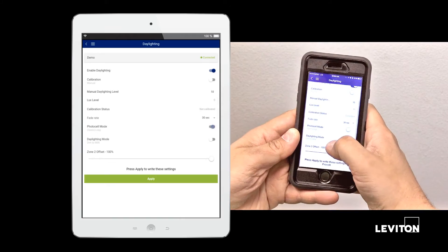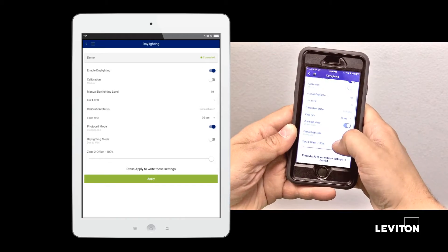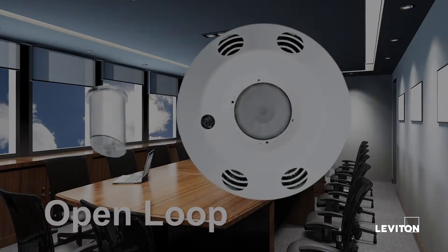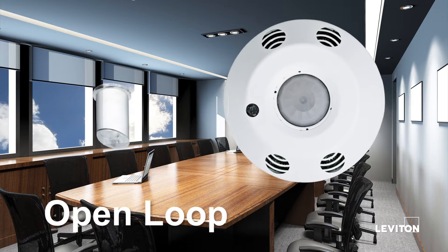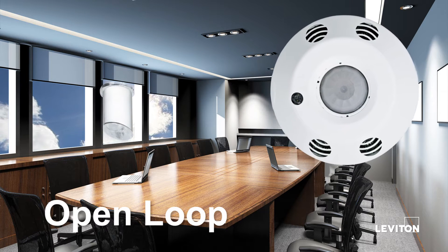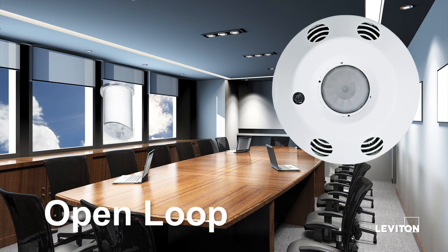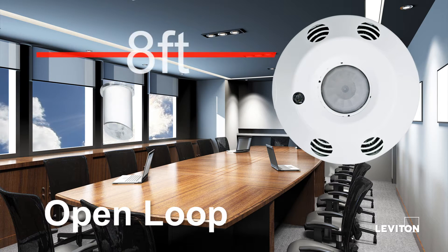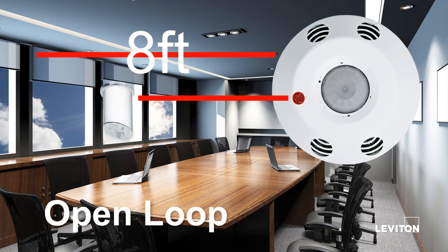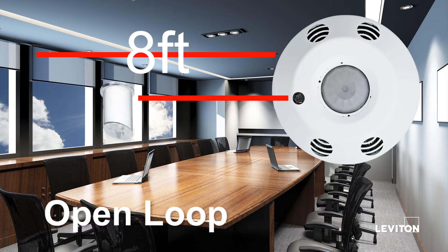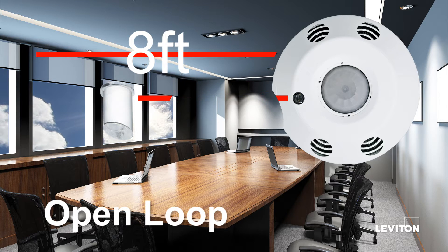Set the photocell mode to open or closed loop. Open loop should be used with the angled light pipe supplied in the package with the PRC. And the PRC should be installed within 8 feet of the window with the angled light pipe directed towards the window. This mode adjusts the lighting in the space based off of natural light levels outside.